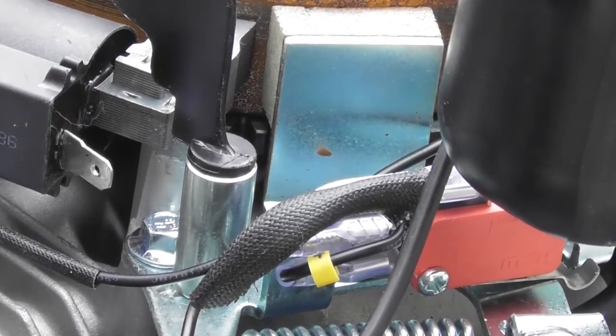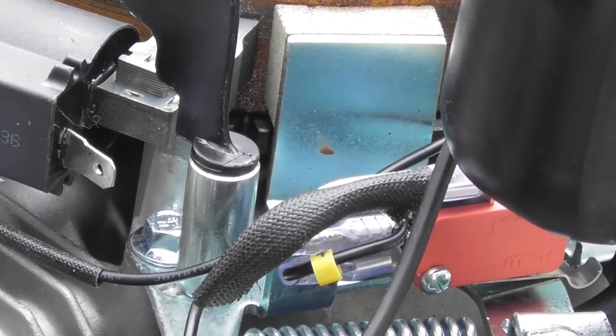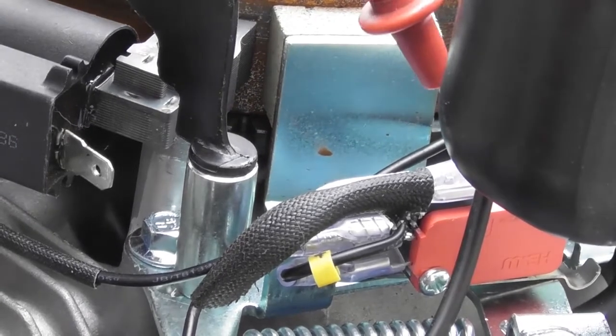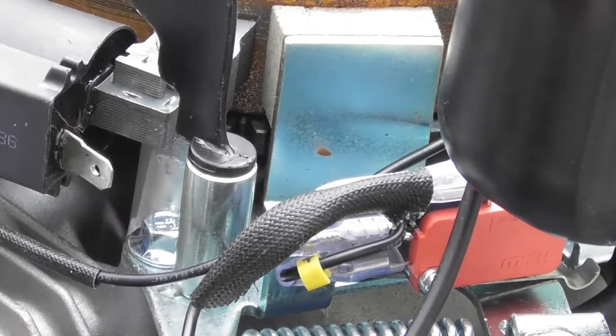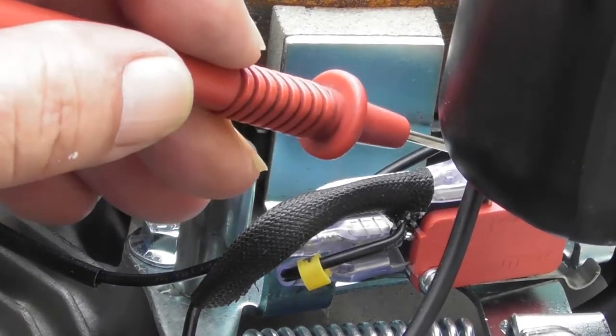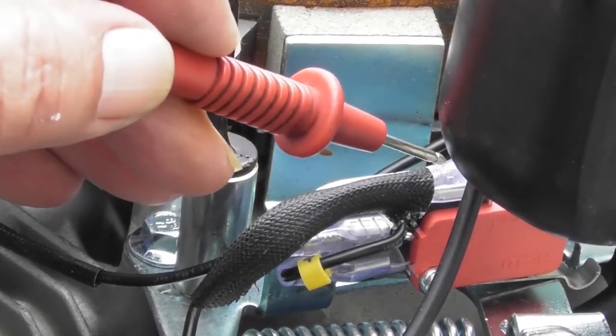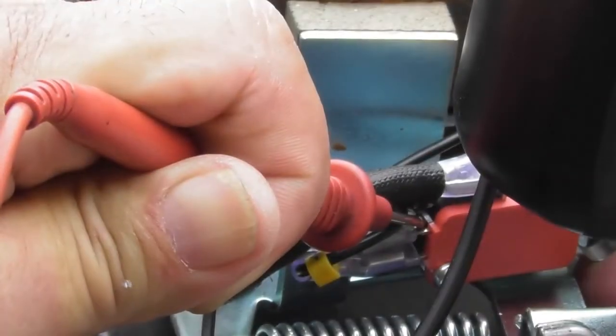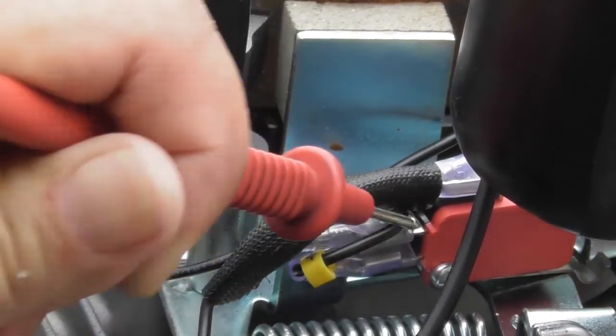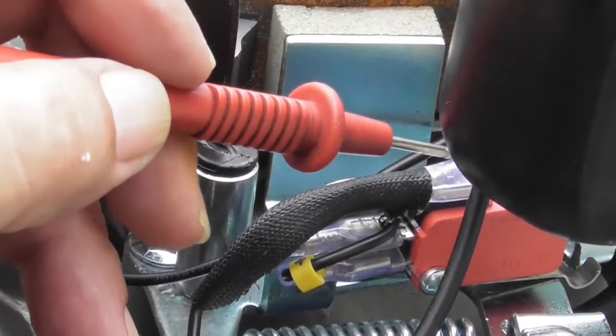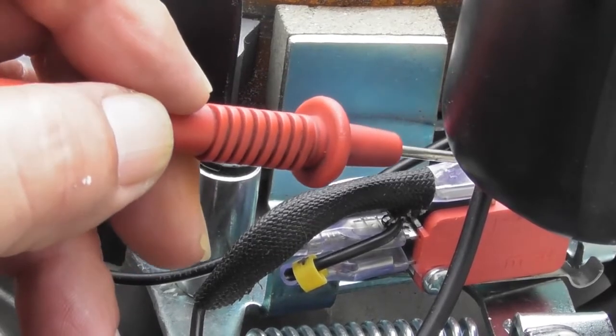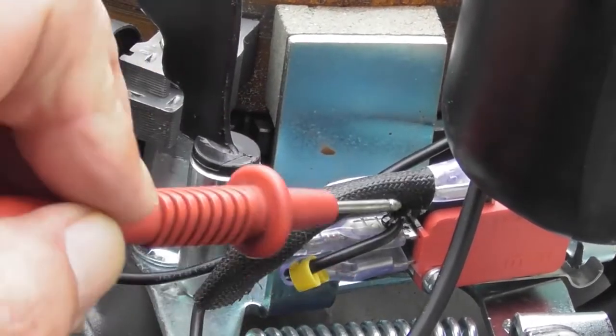I'll set my meter up for a beep test to check. I put my probe in this terminal, the negative probe in this terminal on the top, and I should get a beep there. Push the switch, gone. If I come on the top one, no beep; push the switch, and a beep. So depending on the position of the switch is whether negative comes out of the bottom or out of the top.